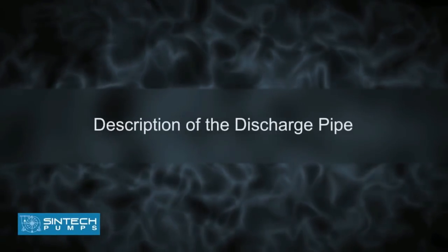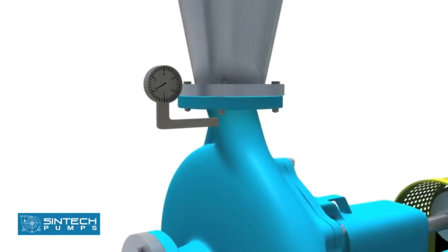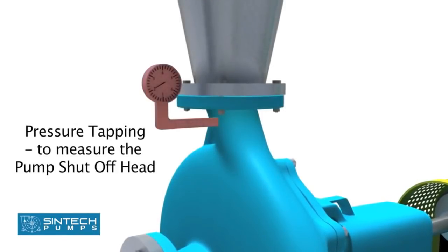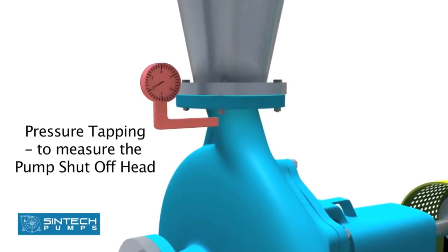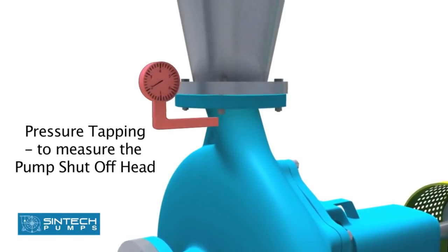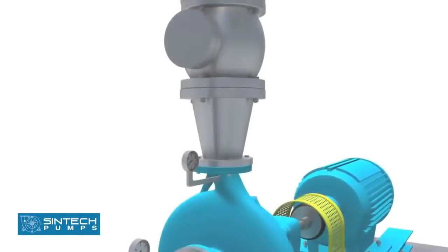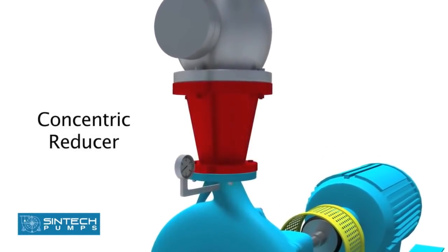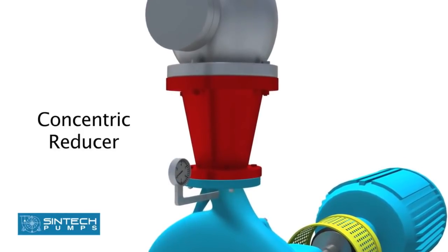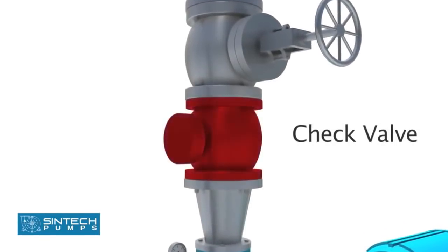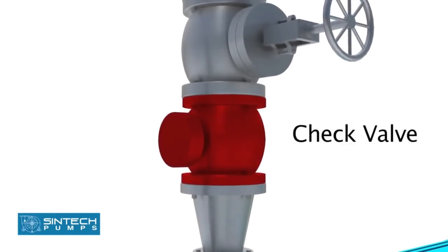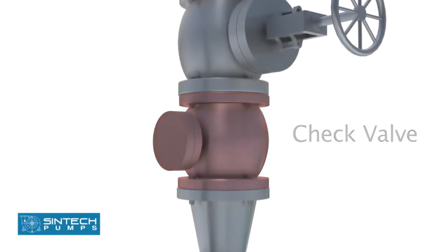Description of the discharge pipe: There should be a pressure tapping as close to the pump outlet and before the isolation valve as possible to measure the pump shut-off head. Concentric reducers are installed in the discharge pipe to minimize friction losses. The check valve used in the discharge should be of non-slam type to prevent hydraulic shocks.